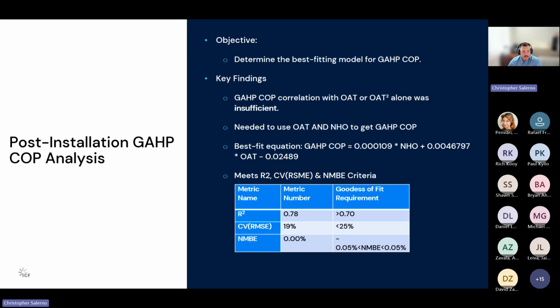And so we want to go into the actual post analysis and what we found. So here, what we try to do is fit a model for the actual GHP COP. And fortunately, since we know the heat pumps are directly related to the OAT, since they exchange heat with the outside environment, we found that the GHP's performance tracked well with OAT, but also the NHO as well. So we found that it was necessary to use OAT, outside air temperature from the nearby weather station, and NHO, which is the net heat output, basically what the boilers are supplying to the system. And so that's how we were able to fit.